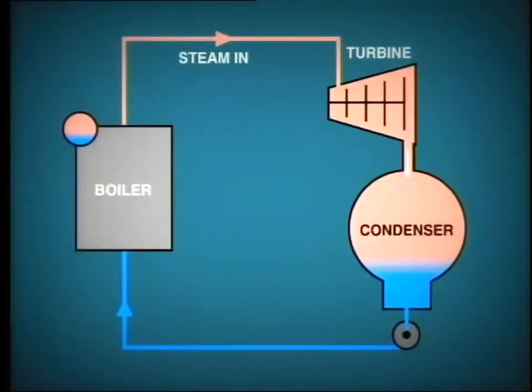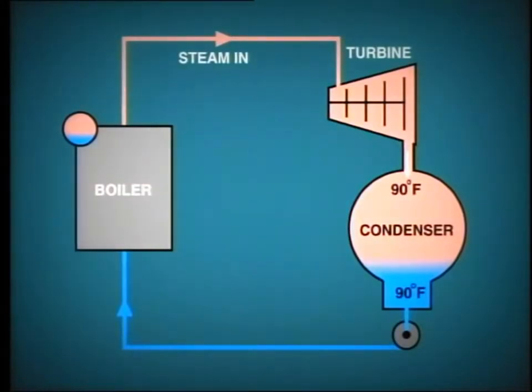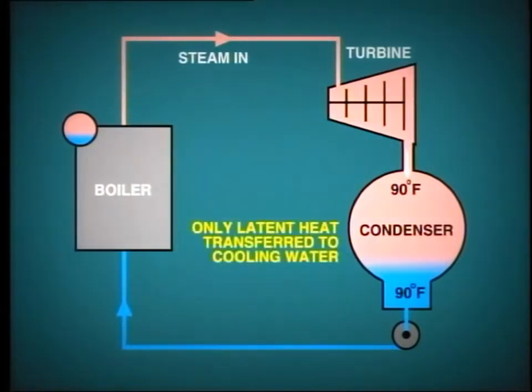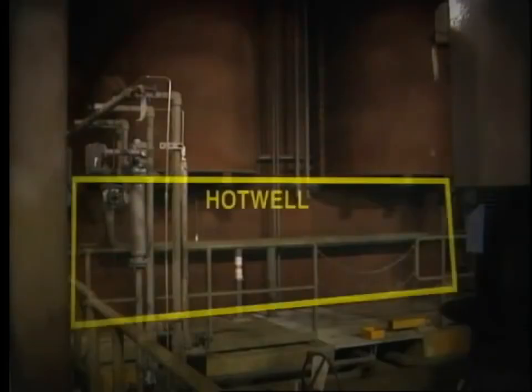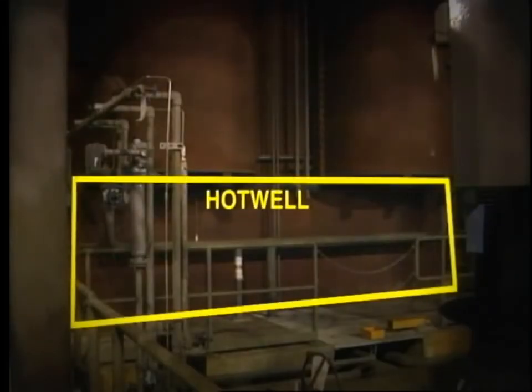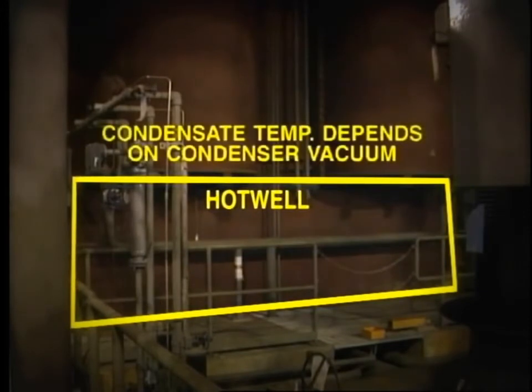The condensate collecting in the bottom of the condenser will ideally be at the same temperature as the steam exhausting from the turbine. In this situation, it is only the latent heat that is transferred from the steam to the condenser cooling water as the steam condenses. The actual temperature of condensate in the hot well is probably within the range of 80 to 100 degrees Fahrenheit, depending upon the vacuum in the condenser, and this in turn is dependent upon other conditions such as cooling water temperature.